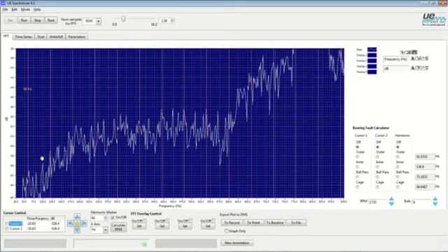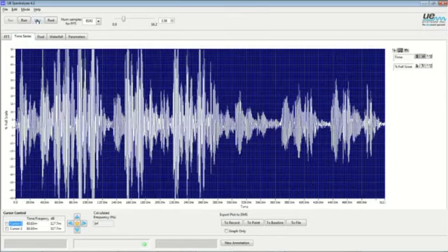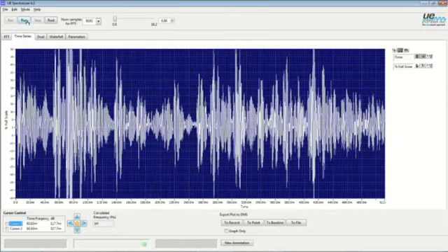In looking at this one, there's one hit on 120 hertz here, very small, but no more until we get out here to 480 hertz and 530 right there. But notice the abundance of frequency content. The tonal quality of the recording suggested popping noises. That's characteristic of discharges as we hear it. But to visualize it, once again, we have to come to the time analyzer, and I'll let this play one more time.